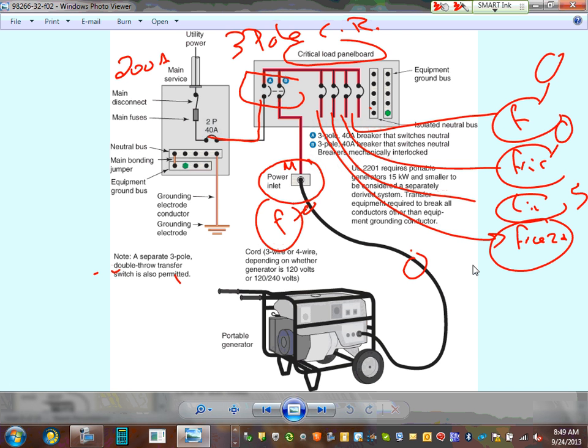Right now we're running on utility. If you're running on utility, each one of these guys has a disconnect like these. Three disconnects: this is hot one, hot two, and this is the neutral. Each one of them. So you break the two hots and neutral at the same time. When I connect here, I connect two hots and neutral, and break two hots and neutral. You break here, you connect here. That's how they work.